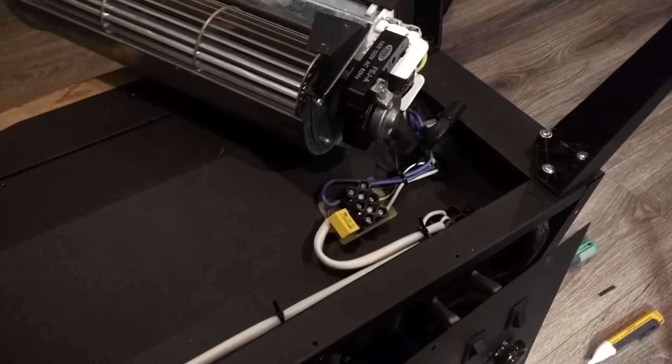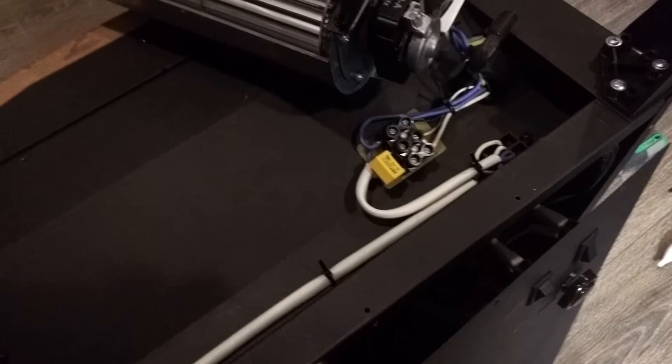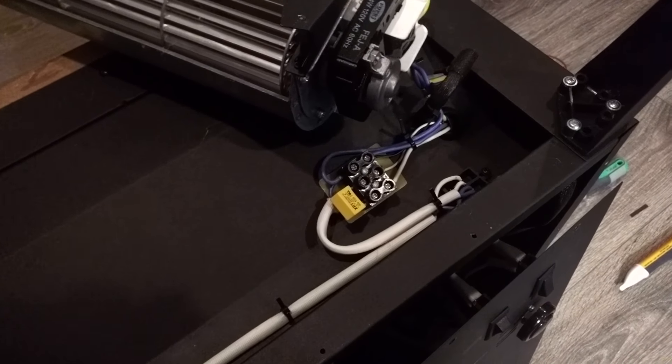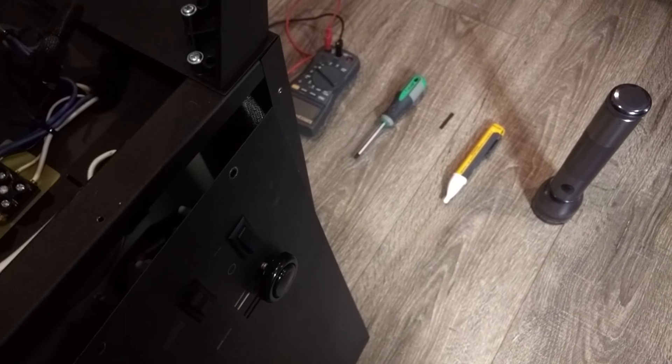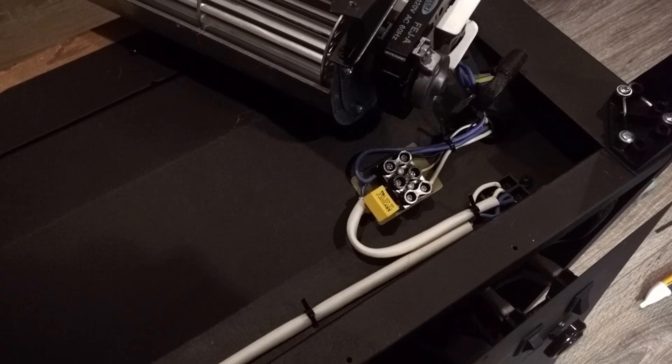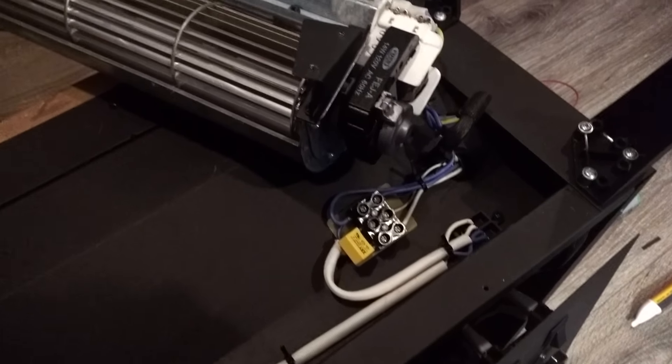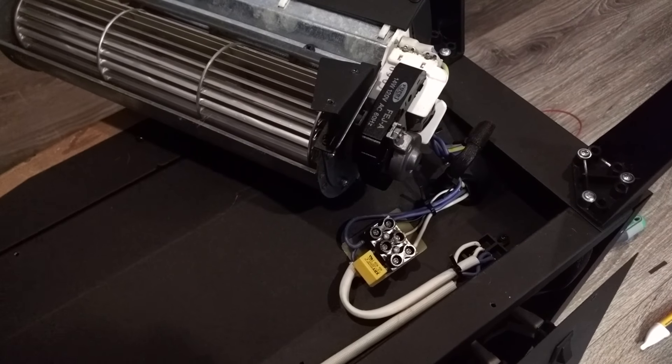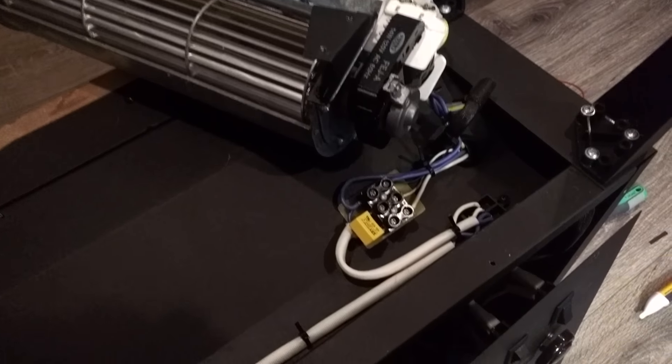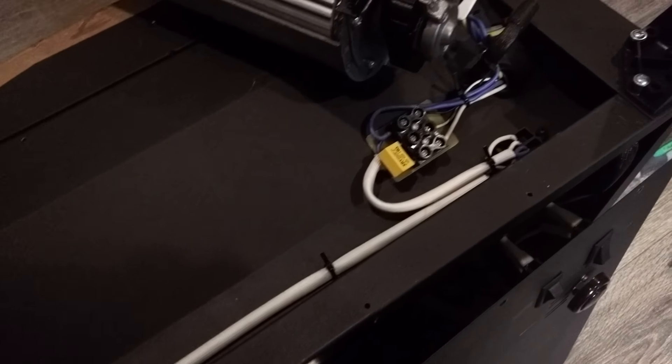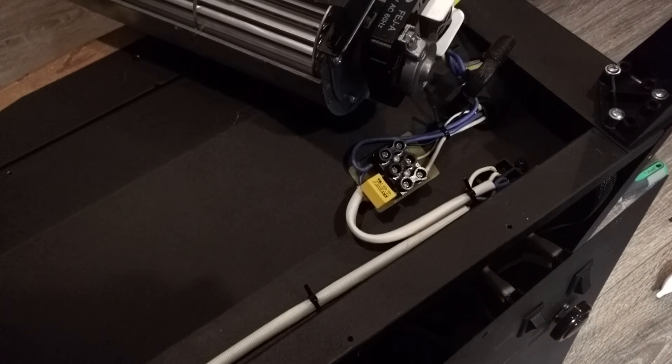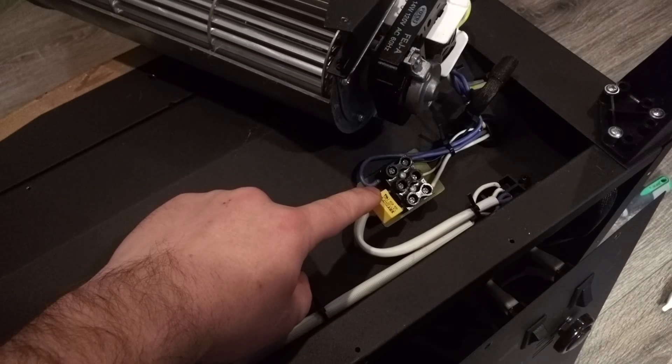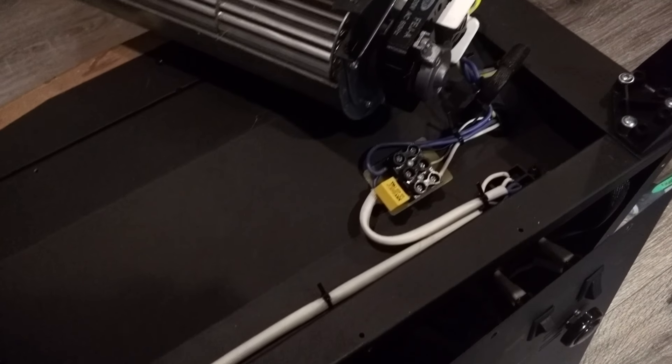Then I started tracing the wires back to the bottom of the unit where the heater is. It was really weird because I have my little Fluke AC wireless checker, and it looked like the heater was receiving power. It looked like the fan was receiving power. I was trying to track down to see if there was a fuse of any kind, and I couldn't find one. There's this little guy right here, but that's a safety capacitor, not a fuse.